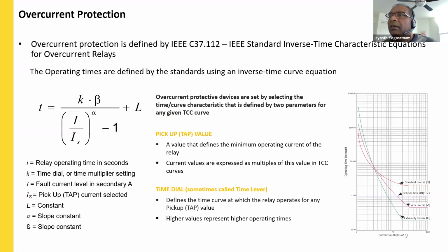And the second parameter we talk about is the time dial. Changing the time dial will move the curve vertically upwards and downwards. The time dials are selected based on the time coordination with the closest upstream device and the closest downstream device. So this time dial will help to discriminate one device over the others, and it will allow the relay to trip on the fault which falls within that zone.